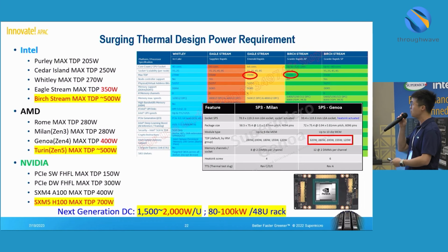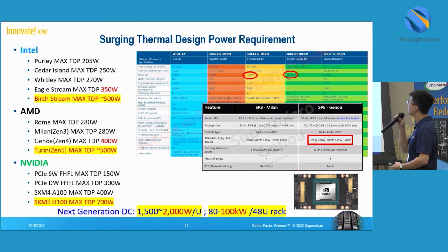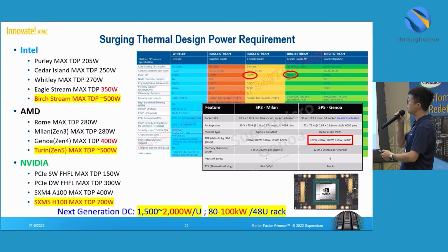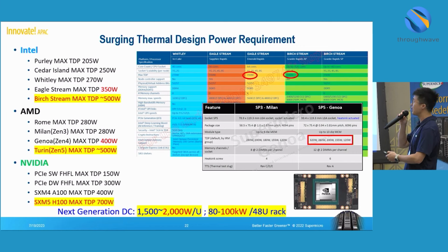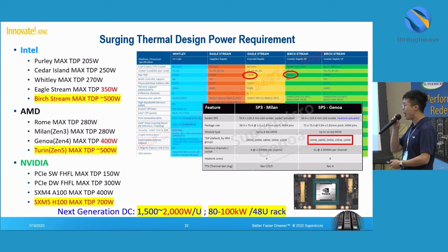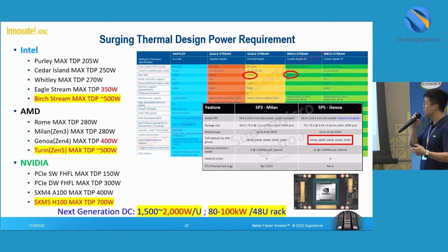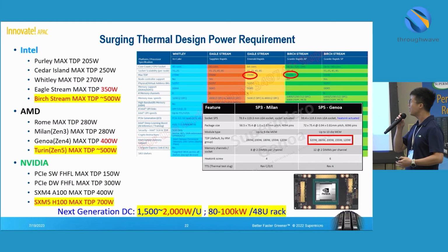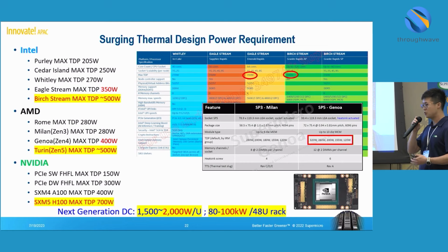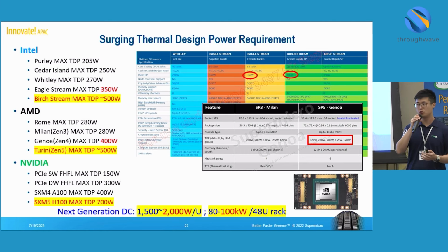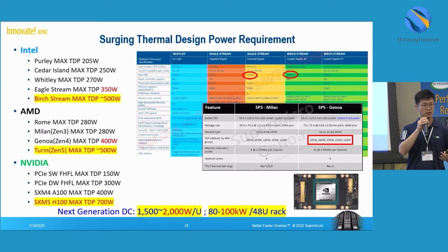The first reason is the surging thermal design power requirement. Let's take Intel CPU for example. The CPU TDP was only 205 watts per platform, but it increased to 350 watts in the current EagleStream platform. The CPU TDP is getting even higher in the next generation Birch Stream platform, around 500 watts. The NVIDIA GPU requires more power too. The previous A100 GPU module was 400 watts, and the current H100 GPU module is 700 watts. So higher CPU and GPU TDP is challenging the current air cooling thermal design solution. That's why you can see many 1U, 2U, or high-density systems have thermal limitations supporting higher CPU TDP.